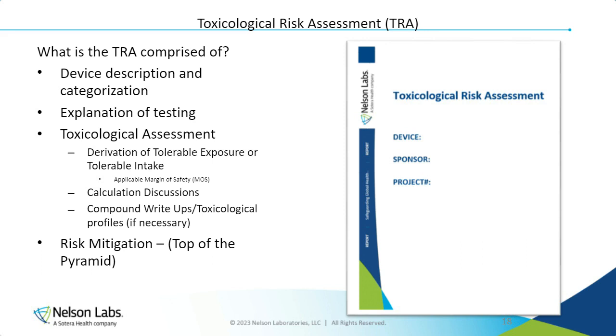Within a toxicological risk assessment, we include device description and categorization, explanation of testing, and then a toxicological assessment of all the analytes seen. We can assess particulates, VOCs, inorganics, and condensate from E&L all within a single TRA. Here, we can derive various tolerable exposures and tolerable intakes, ultimately providing a margin of safety value. We then have a short calculation discussion, and if there are any compounds that are known to have adverse toxicological effects, we can provide full multi-page write-ups. If toxicological safety is not supported, we may move on to the top of the pyramid, risk mitigation. However, risk mitigation comes with regulatory risks and it must be handled appropriately.